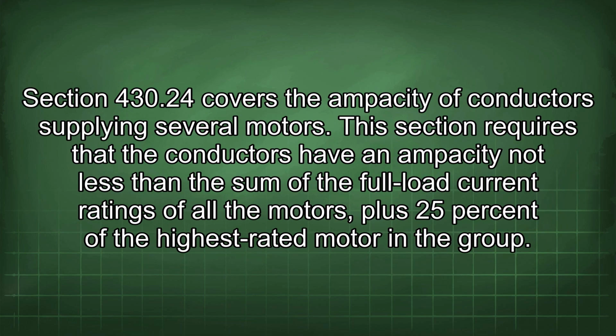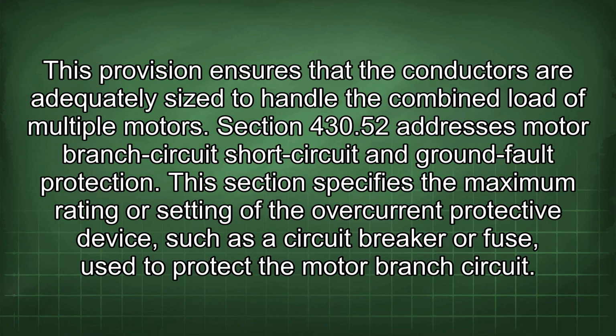Section 430.24 covers the ampacity of conductors supplying several motors. This section requires that the conductors have an ampacity not less than the sum of the full load current ratings of all the motors, plus 25% of the highest rated motor in the group. This provision ensures that the conductors are adequately sized to handle the combined load of multiple motors.